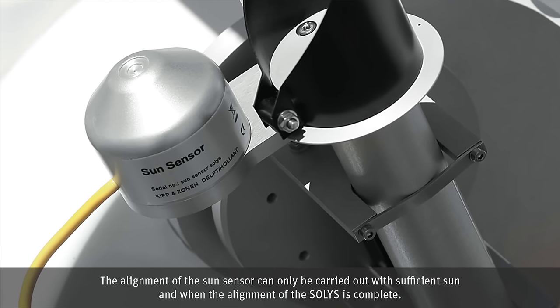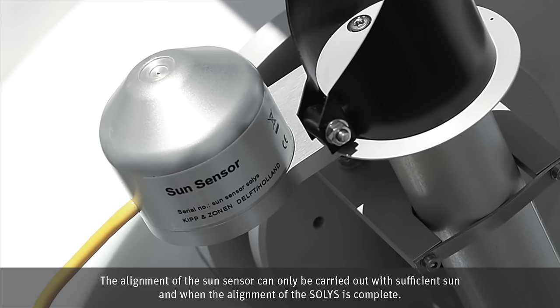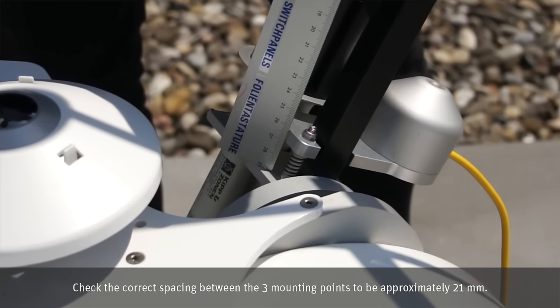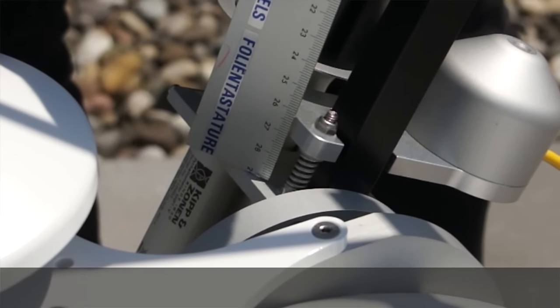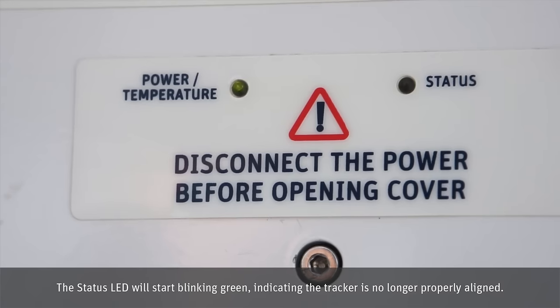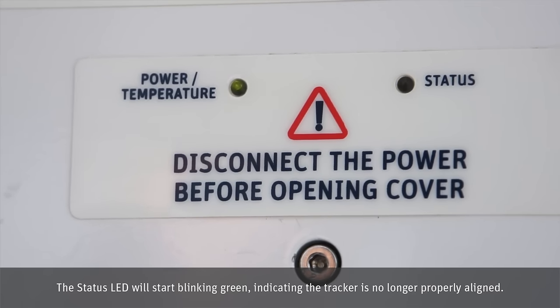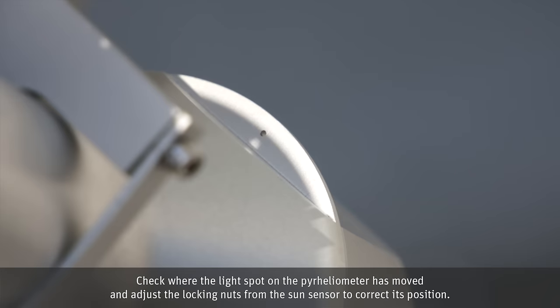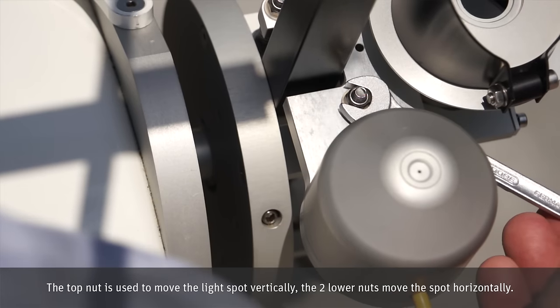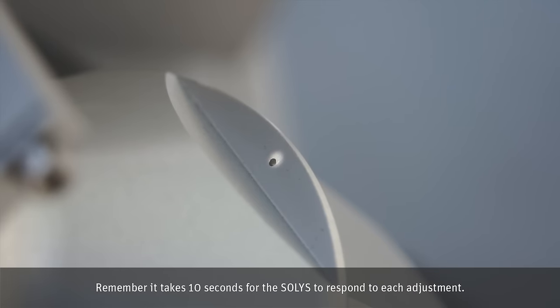The alignment of the Sun sensor can only be carried out with sufficient sun and when the alignment of the SOLYS is complete. Check the correct spacing between the three mounting points to be approximately 21 mm. Connect the Sun sensor cable to the bottom of the SOLYS and screw the locking ring hand tight. The status LED will start blinking green, indicating the tracker is no longer properly aligned. Check where the light spot on the pyrheliometer has moved and adjust the locking nuts from the Sun sensor to correct its position. The top nut is used to move the light spot vertically. The two lower nuts move the spot horizontally. Remember, it takes 10 seconds for the SOLYS to respond to each adjustment.